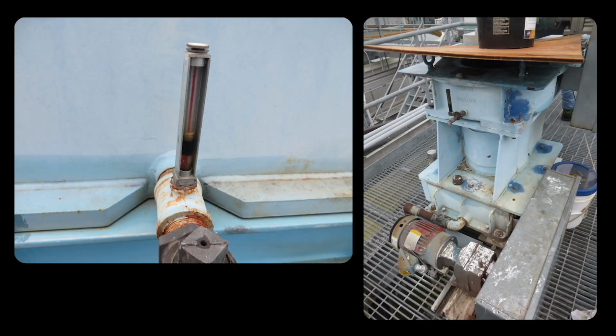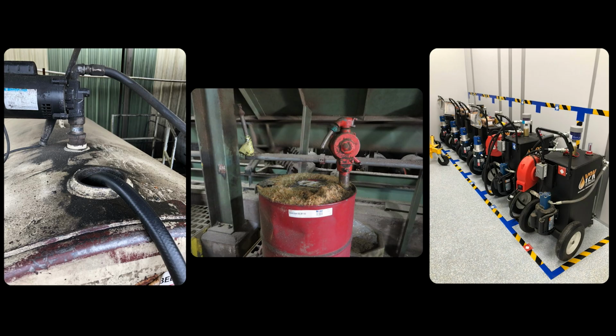More examples. Here is oil level. Simple thing to check. In this case, it's already below the marking that says it's the lowest level. But if you look closer at that oil, you can see there's water in there, and plus it's very dark. So it looks like there's something wrong there with water in the oil, and when we looked in the gearbox, there was water in there. So these are things that are going to damage your bearings and the gears and the seals in there, of course.